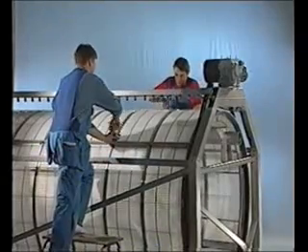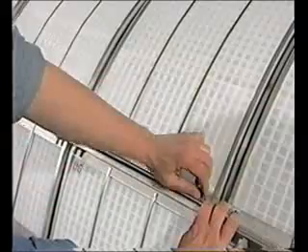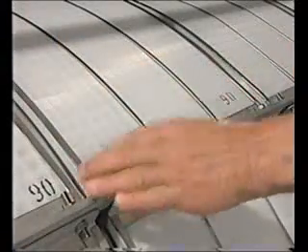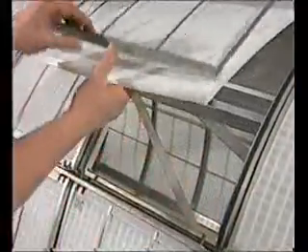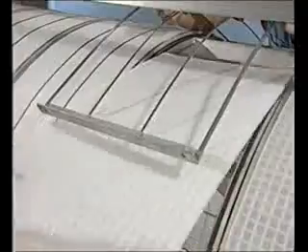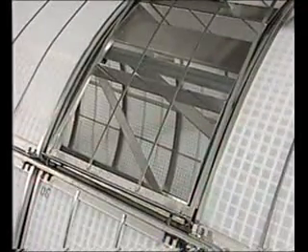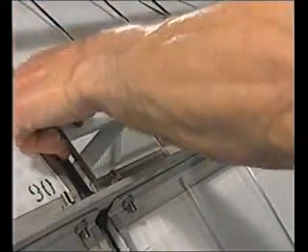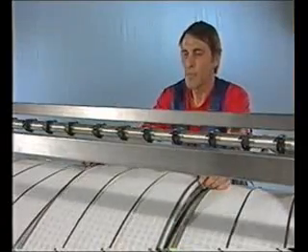The patented filter panels are available in a standard module design and fit all sizes of drum filters. The filter panels consist of a polypropylene support grid and a welded microscreen cloth manufactured in polyester or stainless steel. The filter panel is held in position by a metal frame, which is attached using two nuts on each of the short sides. The rubber gasket, which is fixed to the drum, seals the outer edges of the filter panels.